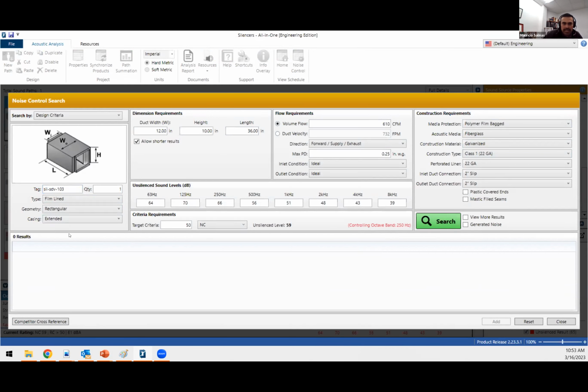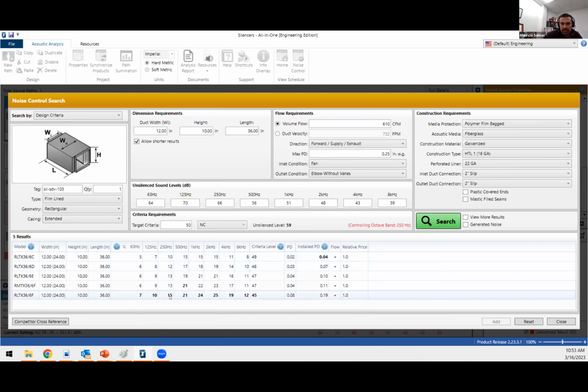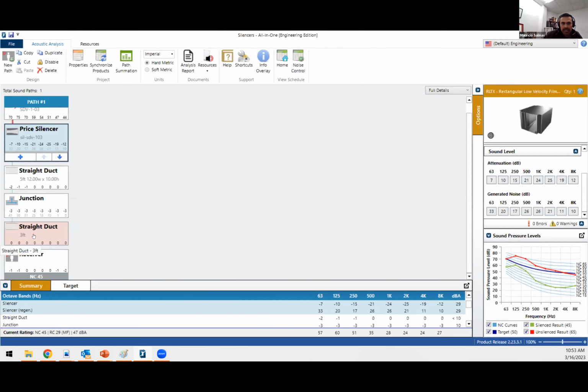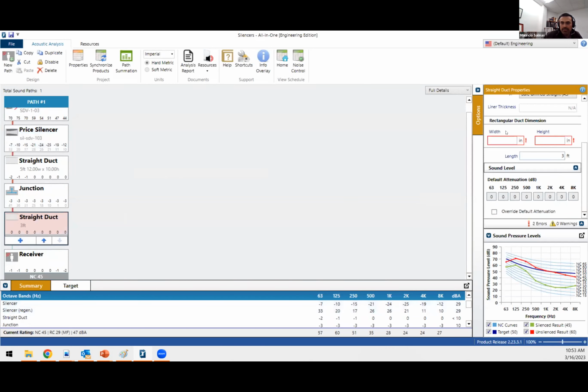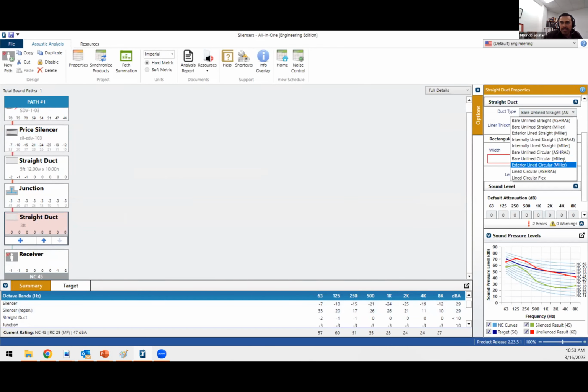You want to make it extended casing because if you're an expert like I was and I am, you know that the lower bands are driving that sound. You're going to have some system effects. And because this is probably really close to the occupied space, I'm going to beef up the casing. I'm going to try to look for a silencer that meets that. So in this specific case, this gets me under NC 50 in that space. And when you go and look at that, you're at NC 45 in the space. All right, loud and clear.